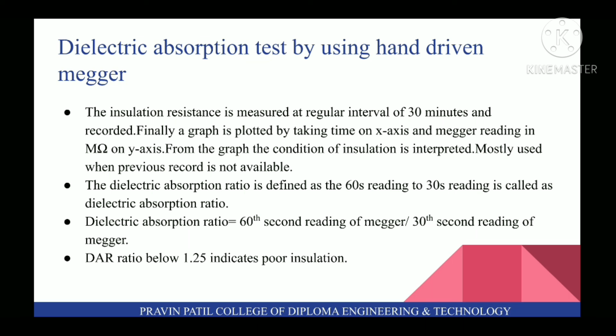The dielectric absorption ratio is defined as the 60-second reading to the 30-second reading. It is called the dielectric absorption ratio. The dielectric absorption ratio is equal to the 60th second reading of the Megger upon the 30th second reading of the Megger. So a DAR ratio below 1.25 indicates poor insulation.